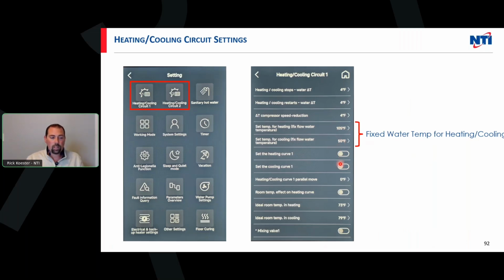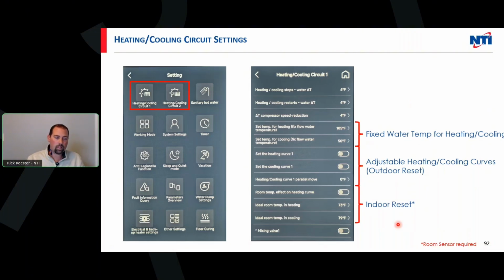We also have the ability to set some curves here. Underneath, you can see adjustable heating curves, which is outdoor reset. Here we have room temperature reset, which is down below it. If I'm doing room temperature reset, I have to add a room sensor, which we provide, but you would have to add it to the system. Outdoor reset's going to be very popular. We actually have a call this afternoon where a big topic is, can I run this like my boiler with an outdoor reset? And yes, we can. So we can have a heating curve as well as a cooling curve, outdoor reset for both modes.